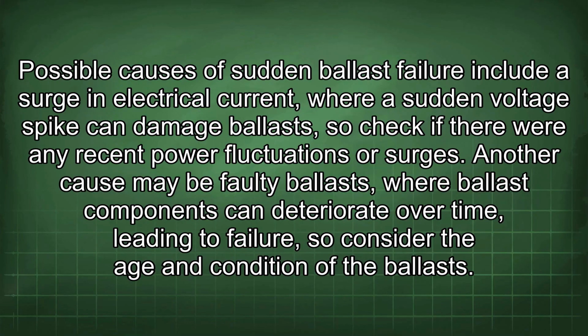Possible causes of sudden ballast failure include a surge in electrical current, where a sudden voltage spike can damage ballast, so check if there were any recent power fluctuations or surges. Another cause may be faulty ballast, where ballast components can deteriorate over time, leading to failure, so consider the age and condition of the ballasts.